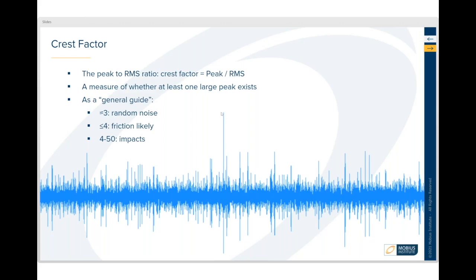We can look at the peaks that are there. We can take the peak value—okay, that's the highest peak—and we can compare that to the RMS value. That gives us something called crest factor.